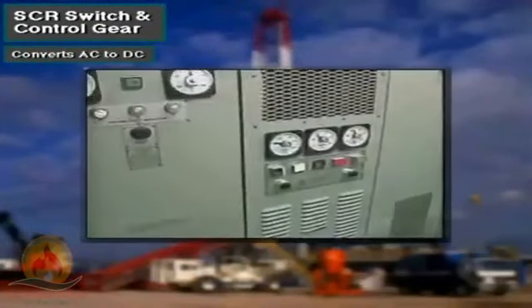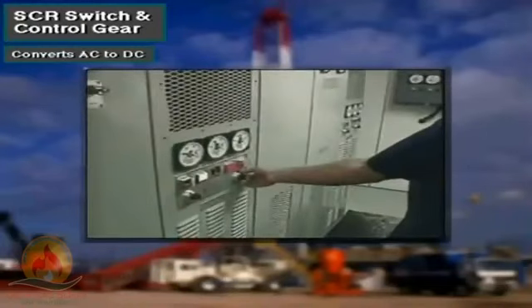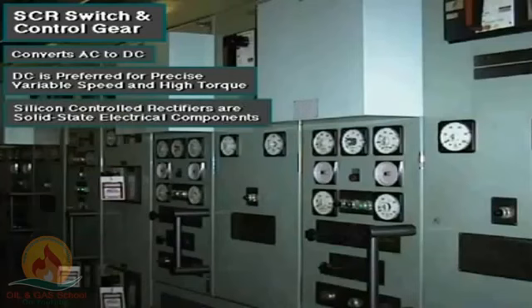Equipment in this electrical cabinet converts, or rectifies is the electrical term, most of the AC current produced by the AC generators into direct current. As mentioned before, rig owners usually prefer DC current for driving the very large equipment that requires precise variable speed control and high torque. The control equipment includes solid-state electrical components called silicon-controlled rectifiers, or SCRs.